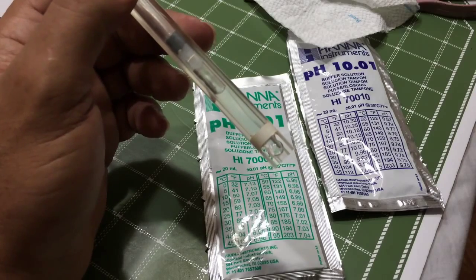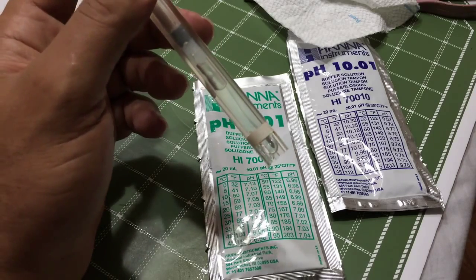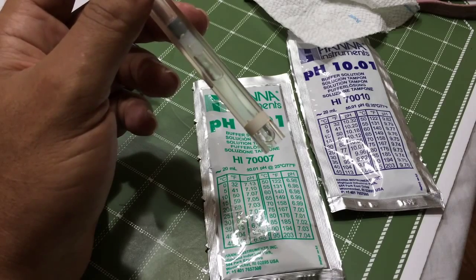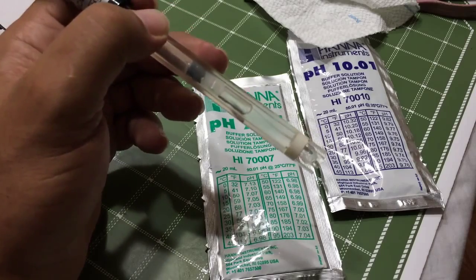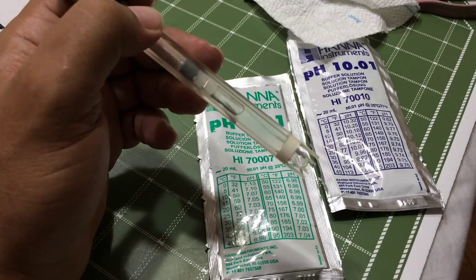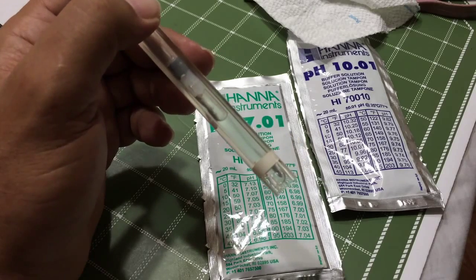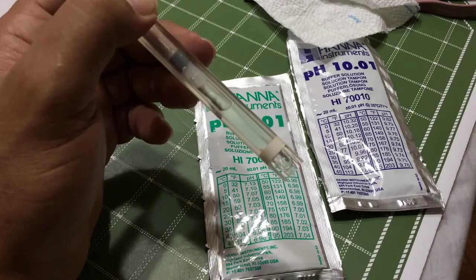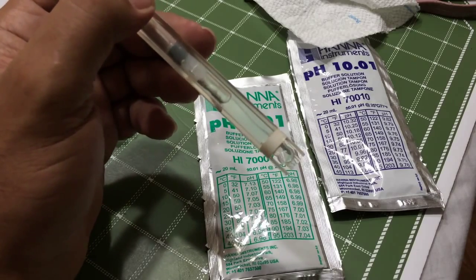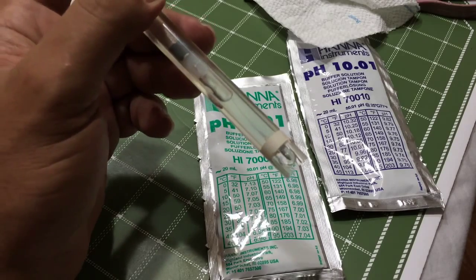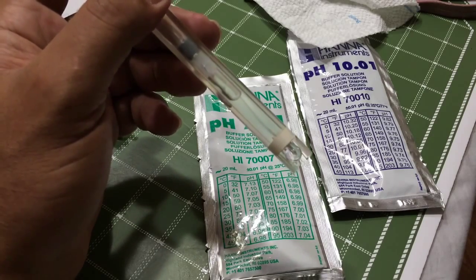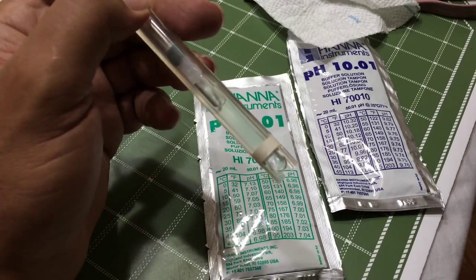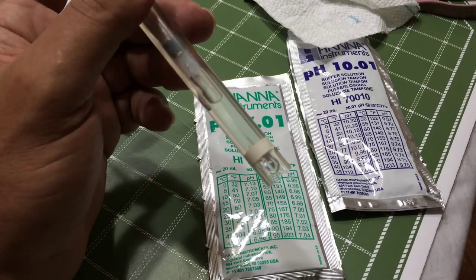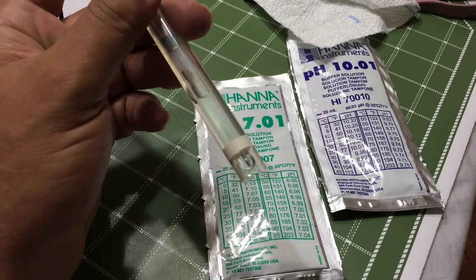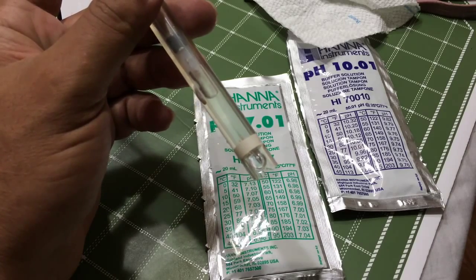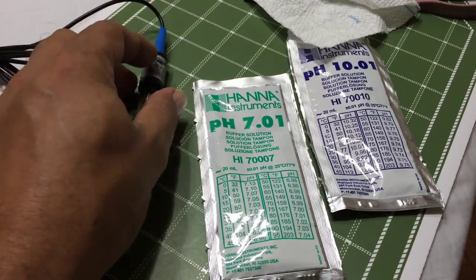Now, if this was a normal probe that had been submerged for a month or something in salt in your sump, you would need to use a cleaner, some form of cleaning agent, and they sell a lot of those probe cleaning agents. Basically, it's slightly acidic, which removes all the algae growth or any kind of growth that is on the probe tip, and cleans it all off. And you can also go online, and they'll show you methods of mixing your own cleaning agent using vinegar or vinegar diluted in water. So that you can look up online.